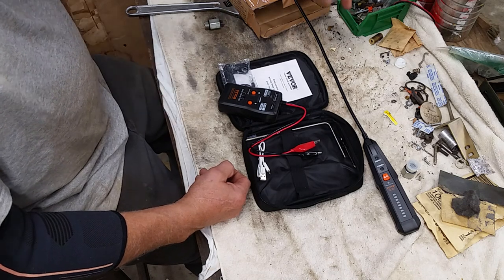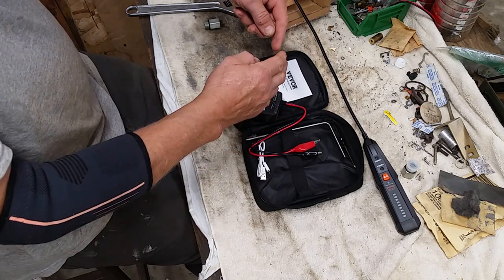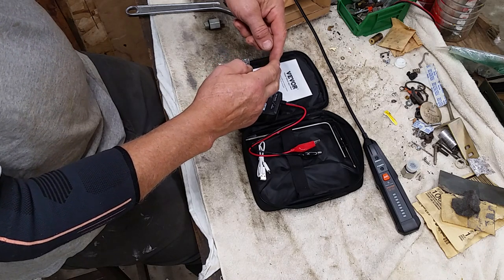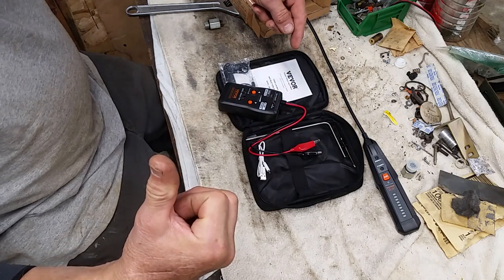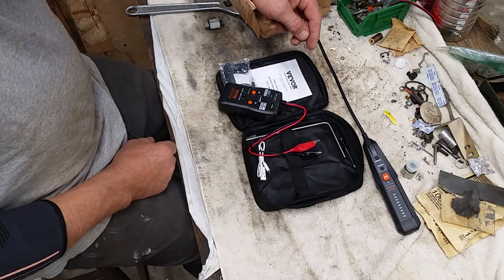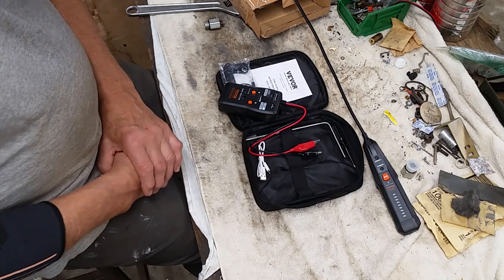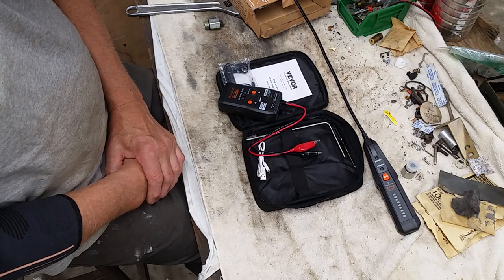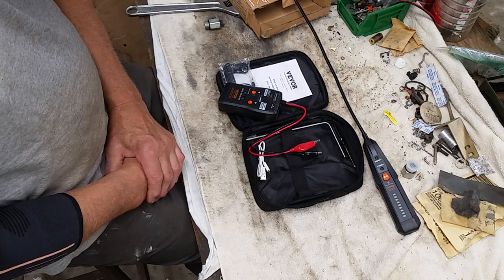The cable coming off of the ledge, I was able to follow that for a little bit. But now I was halfway, almost, you might say, between the cable that was in the air on that end and this, which was a foot and a half above the ground on the other end. And even with my tube, I had trouble finding it. To make matters worse, I was actually trying to find a break in the cable. It was 12-3 with ground. The red wire was broken someplace.